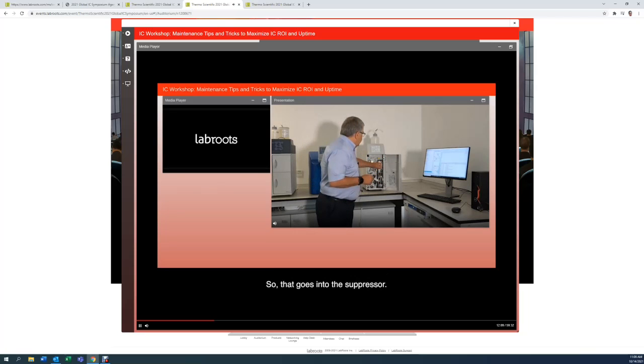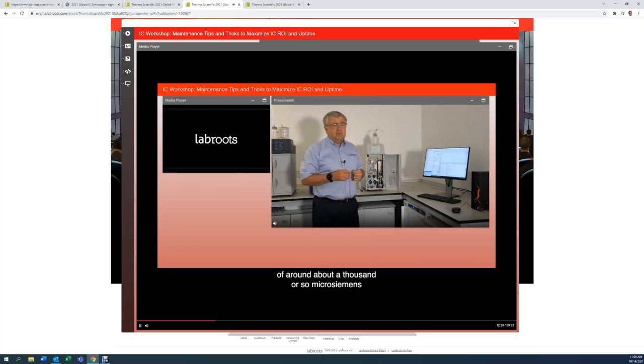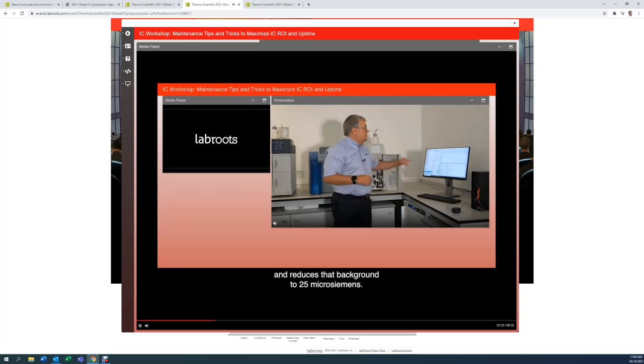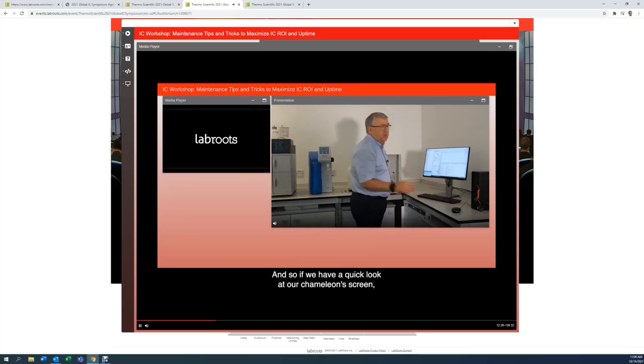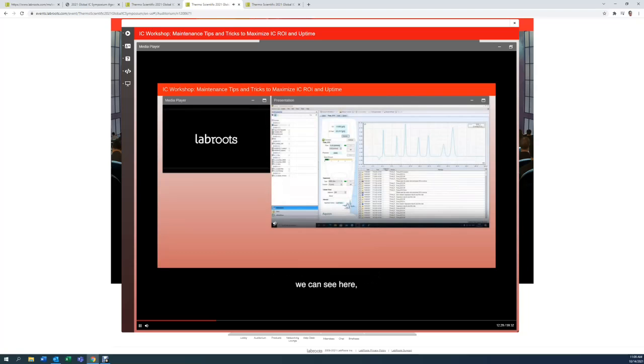So that goes into the suppressor. Now, the suppressor takes the carbonate eluent, which has a background conductivity in the bottle here of around 1,000 or so microsiemens, and reduces that background to 25 microsiemens. So if we have a quick look at our Chromeleon screen, we can see here our background is around 25 microsiemens. The reason is that we're taking the sodium carbonate, removing the sodium in the suppressor and adding a hydrogen ion, forming carbonic acid. And so that is the conductivity of the carbonic acid, a weakly dissociated acid.